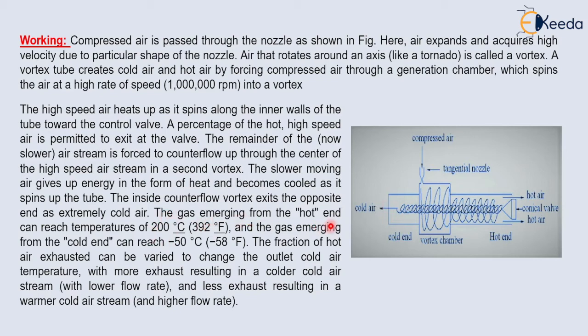The gas emerging from the hot end can reach up to a temperature of 200 degrees Celsius, and gas emerging from the cold end can reach up to minus 50 degrees Celsius. The fraction of hot air exhausted can be varied to change the outlet cold air temperature — with more exhaust resulting in a colder air stream and less exhaust resulting in a warmer cold air stream at a higher flow rate.